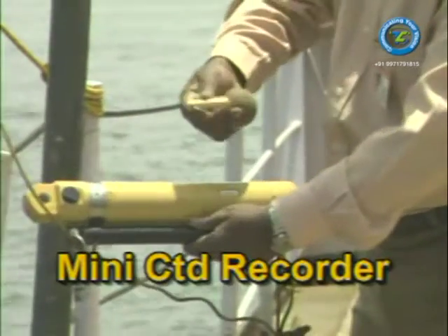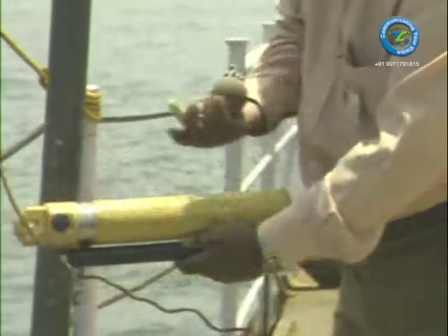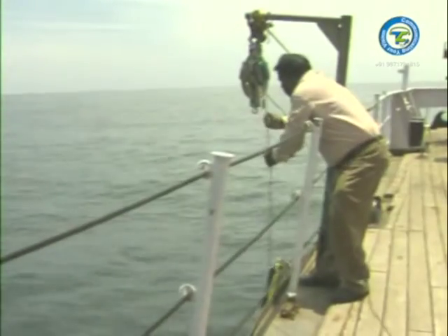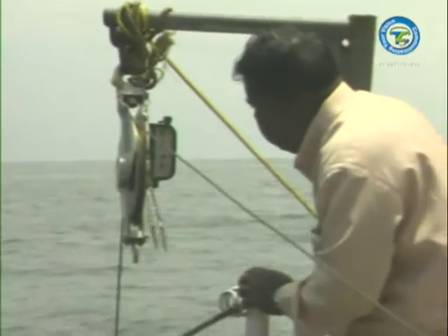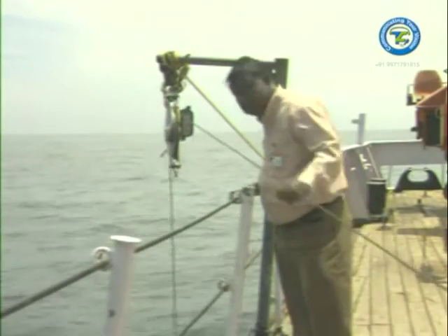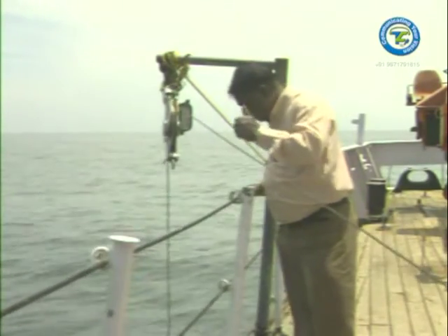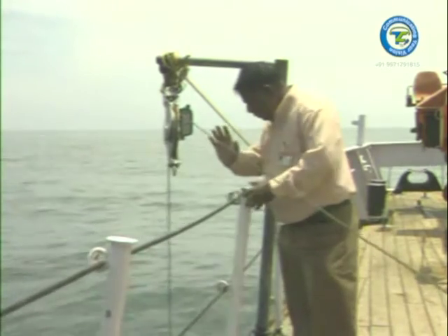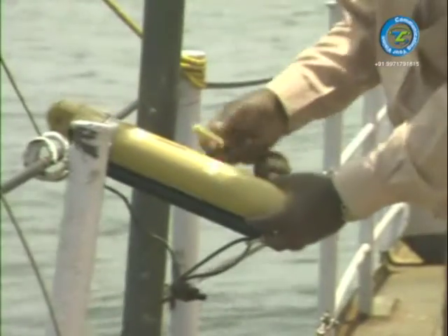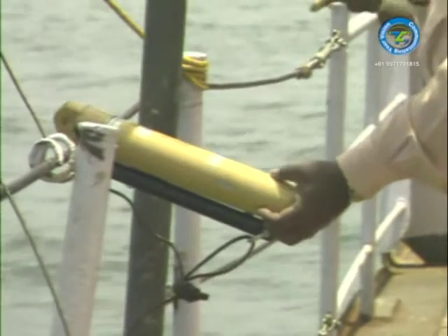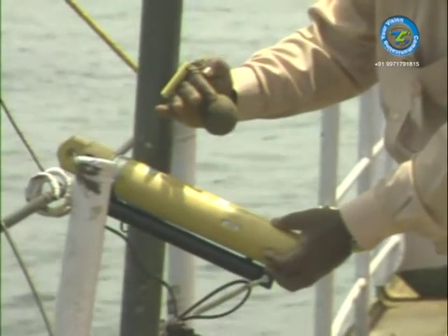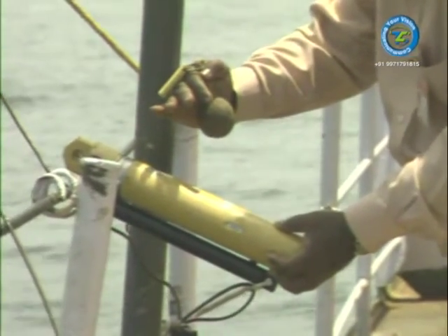Mini CTD recorder, used for recording continuous data on conductivity, temperature and depth in the sea down to 1,000-meter depth. Conductivity and temperature give the salinity. Salinity, temperature and depth are the three major oceanographic parameters which decide the density of seawater and also determine the velocity of sound. These readings are critical inputs in sonar operations.